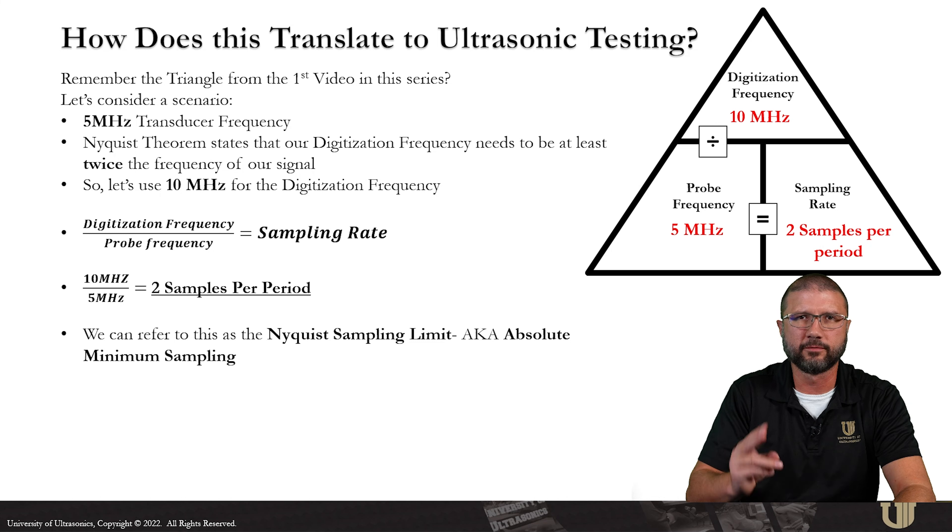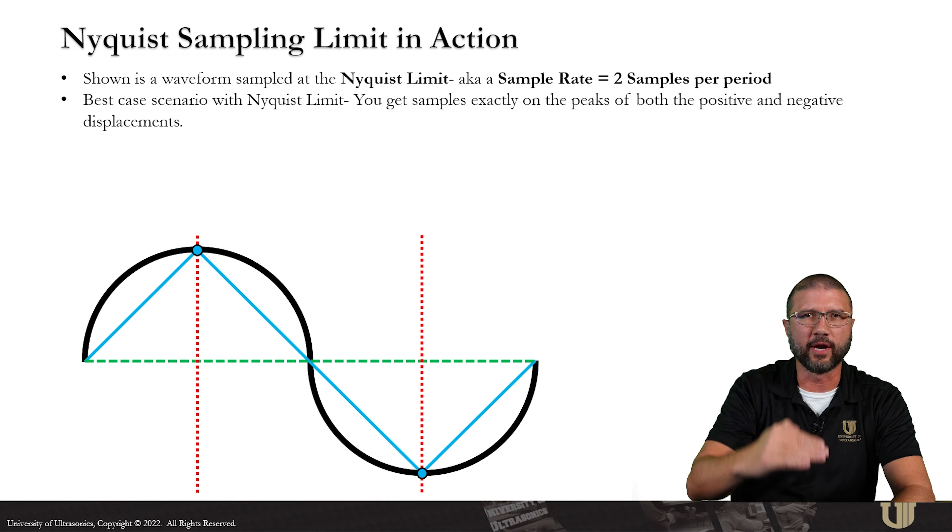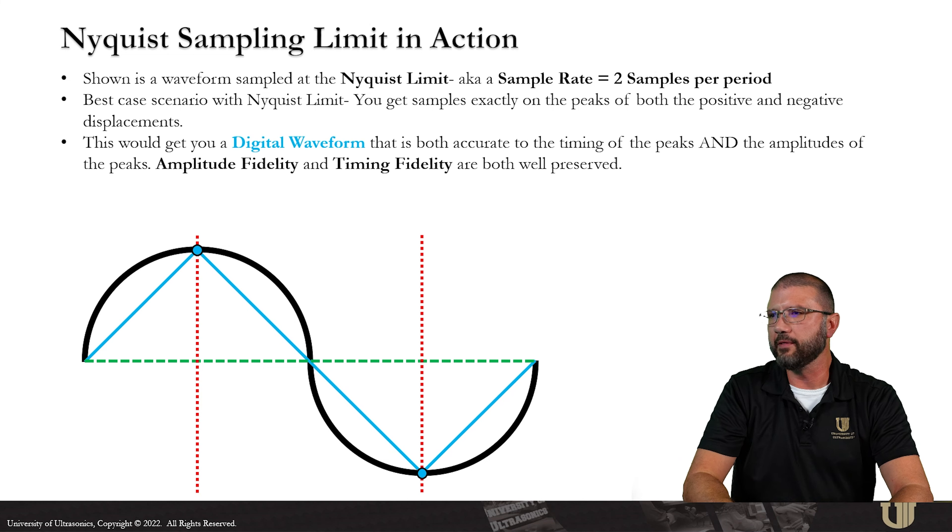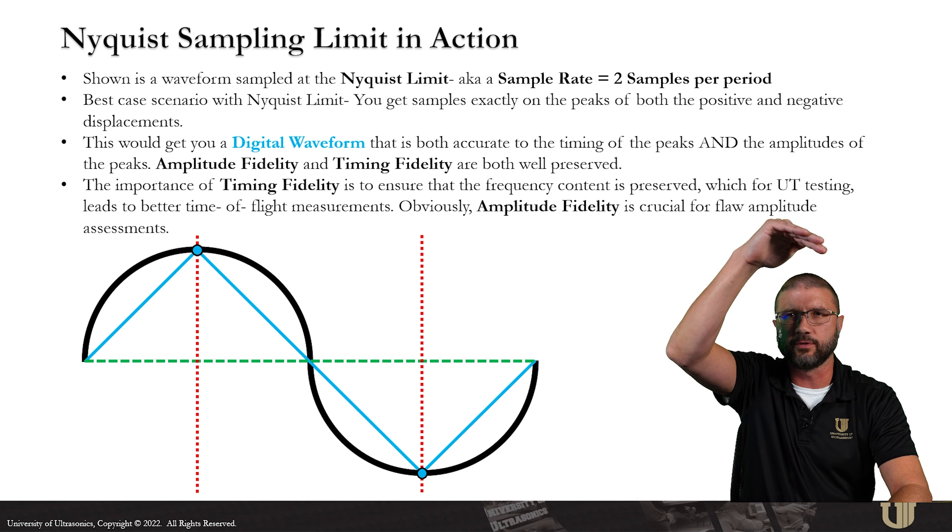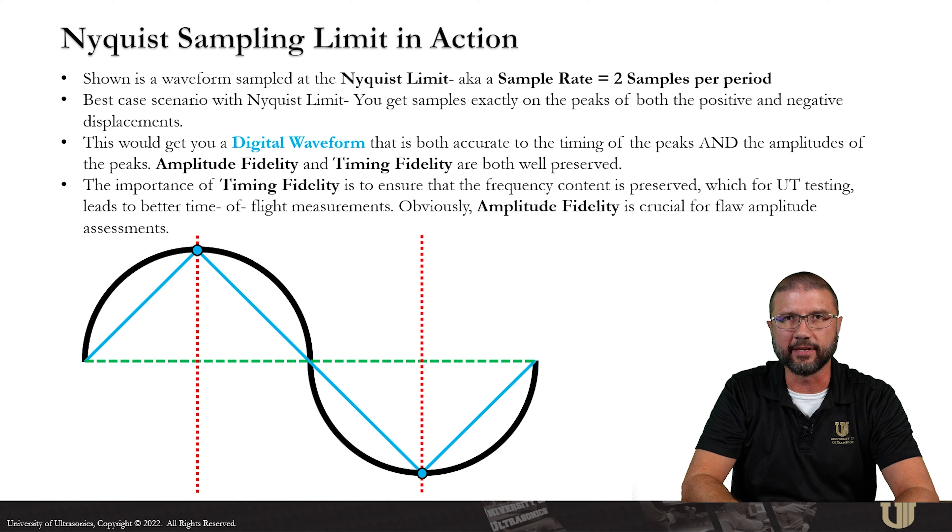So let's see what happens when we put the Nyquist limit in action. We're going to consider a waveform that is sampled at the Nyquist limit, which is going to give us two samples per period. Best case scenario, we get a sample directly on the positive displacement and directly on the peak of the negative displacement. This is going to give us a digital waveform that is both accurate to the timing of the peaks and the amplitude of the peaks. Amplitude fidelity and timing fidelity in this case would both be well preserved. The importance of timing fidelity is to ensure that the frequency content is preserved, which for UT testing leads to better time of flight measurements of our signals. And obviously amplitude fidelity is crucial for our flaw amplitude sizing assessments that we would do for certain code scenarios.